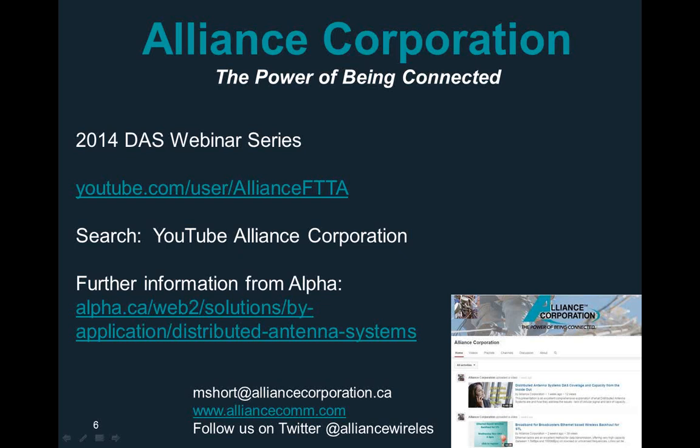Okay, that's a great question. Wi-Fi access points are typically going to be less than 25 watts. They could be powered using the technique that I just mentioned, but more often than not, they're powered with power over Ethernet, by the way, using either Cat 5e or Cat 6 cable. There are power over Ethernet, or PoE, injectors, and they vary depending on the size and the number of ports. But let's say that each port of the injector supplies 30 watts of power. There are devices that are as big as 25 ports. So that's a 750 watt device.